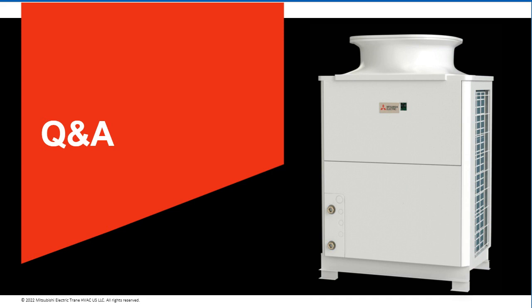Okay, next question. So when stacking the heat pump water heater on the primary side, is it recommended to go parallel or series? We would always want it to be in parallel because we always want that same cold water coming back to each one of the heat pumps. So it would always be in parallel in that nature, so you're not tripping out the heat pump from the previous one bringing heat to it.